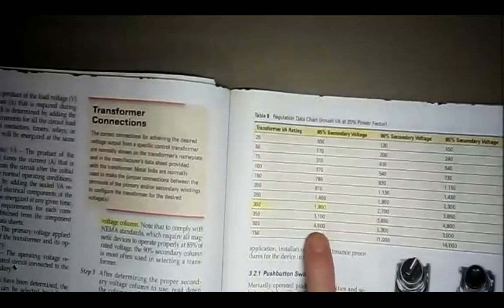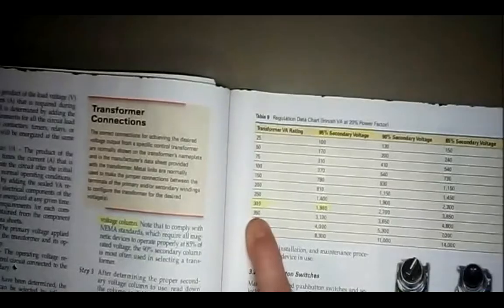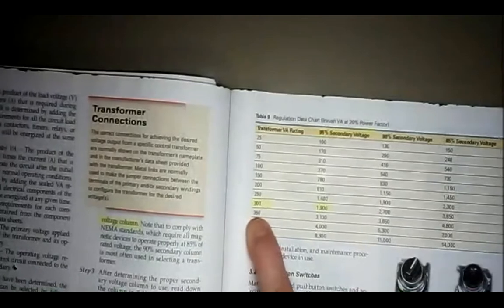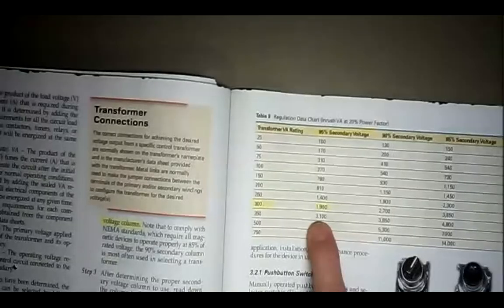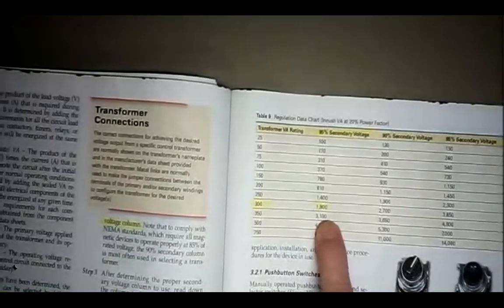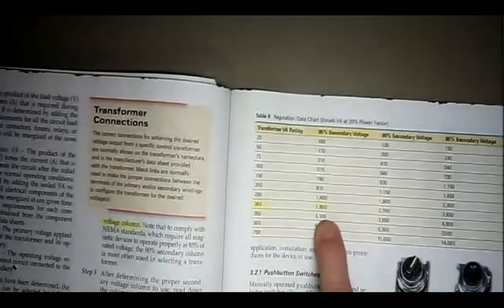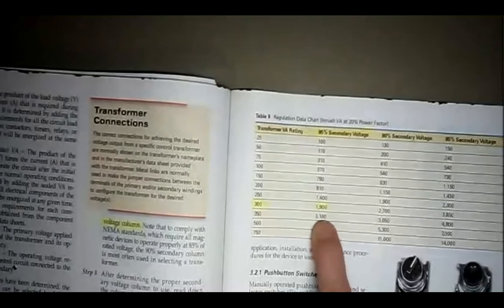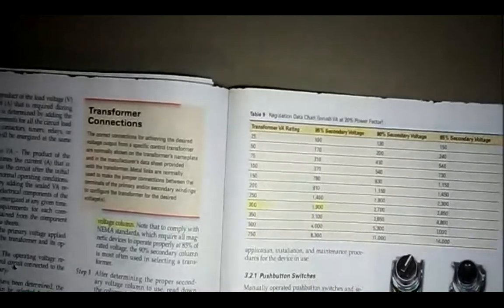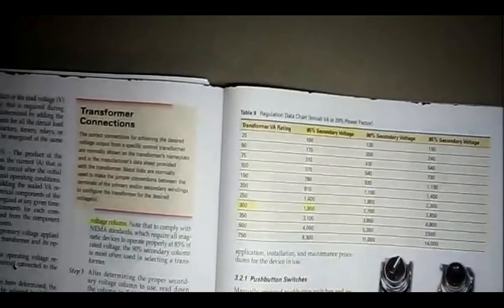So if you have a transformer volt amp rating of 300 volt amps, the 95% secondary voltage might have an inrush of 1900 volt amps. Okay, it's inrush volt amps at 20% power factor, 1900 volt amps. That's how you use that table.